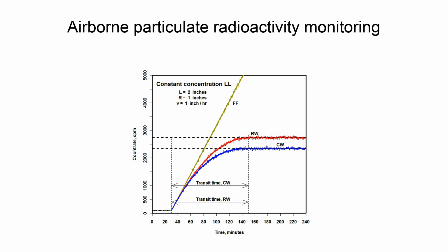This article will focus on CPAM use in nuclear power plants, as opposed to other nuclear fuel cycle facilities, or laboratories, or public safety applications. In nuclear power plants, CPAMs are used for measuring releases of APR from the facility, monitoring levels of APR for protection of plant personnel, monitoring the air in the reactor containment structure to detect leakage from the reactor systems, and to control ventilation fans when the APR level has exceeded a defined threshold in the ventilation system.